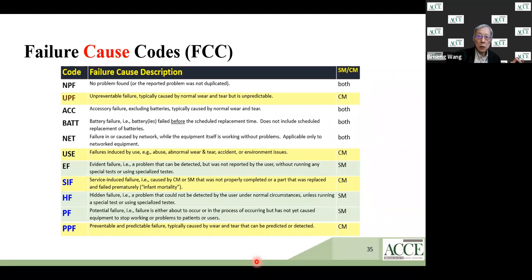Okay, so for example, no problem found. This is very common when you perform a scheduled maintenance inspection and do not find any problem with it. Or somebody said, oh, the equipment is broken. You go there and could not duplicate the problem. So maybe it's a misunderstanding, or maybe there is an intermittent problem there that you don't know about, that you will only find out the next time it happens again.